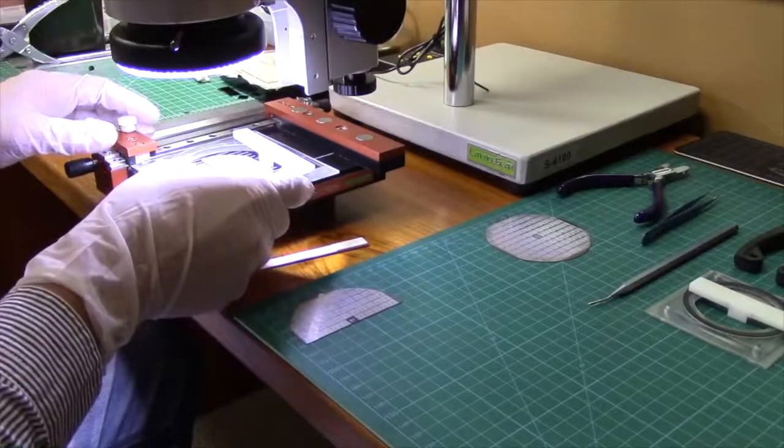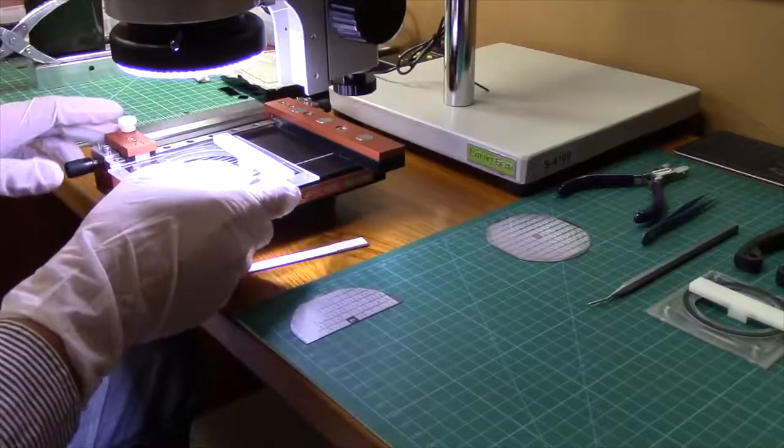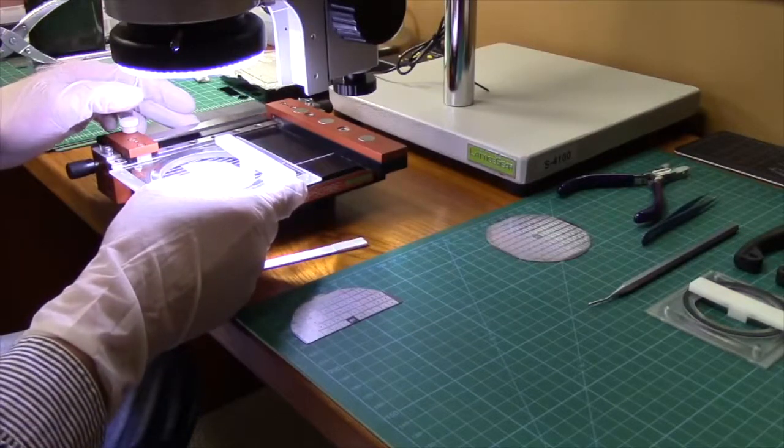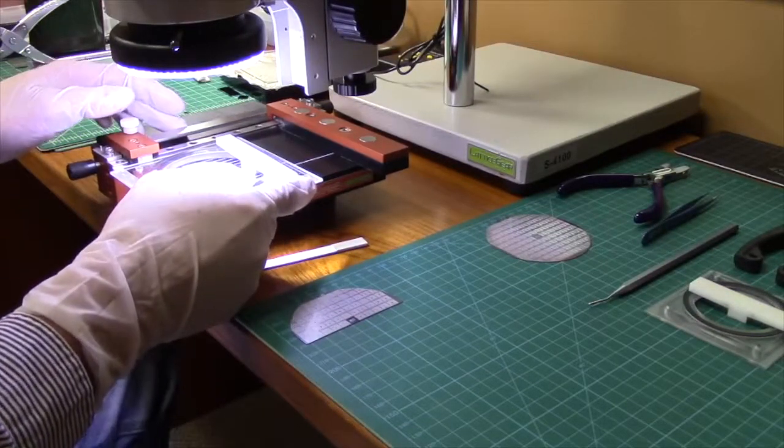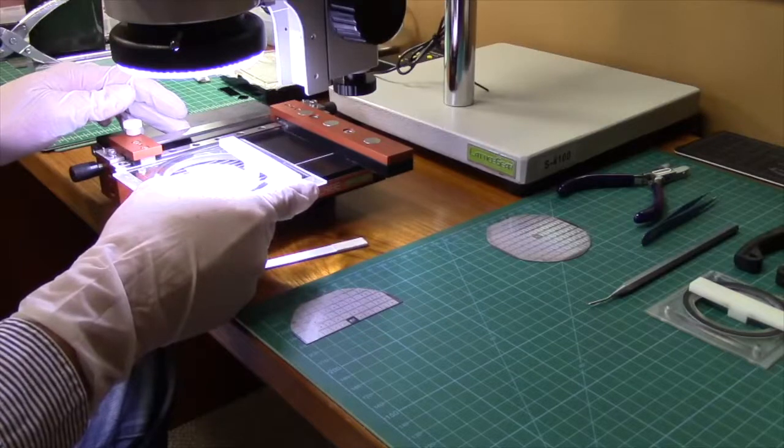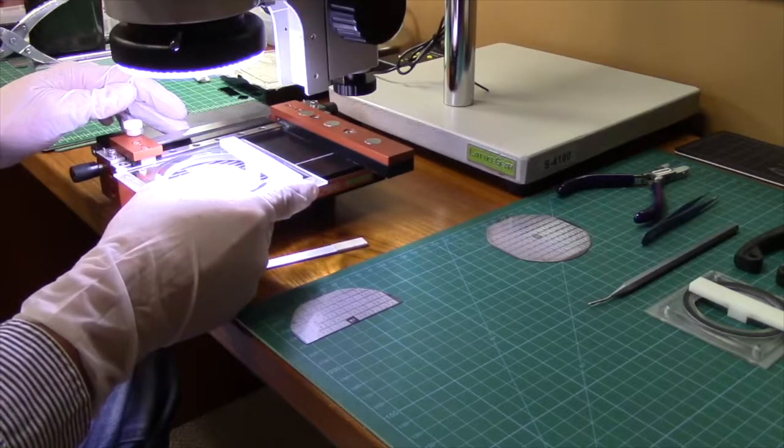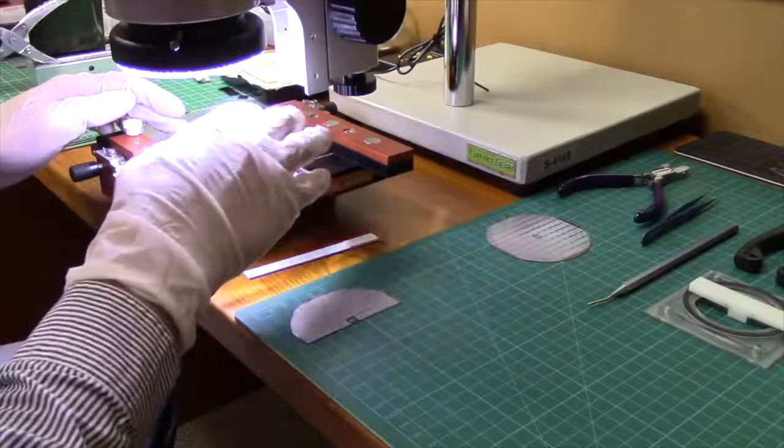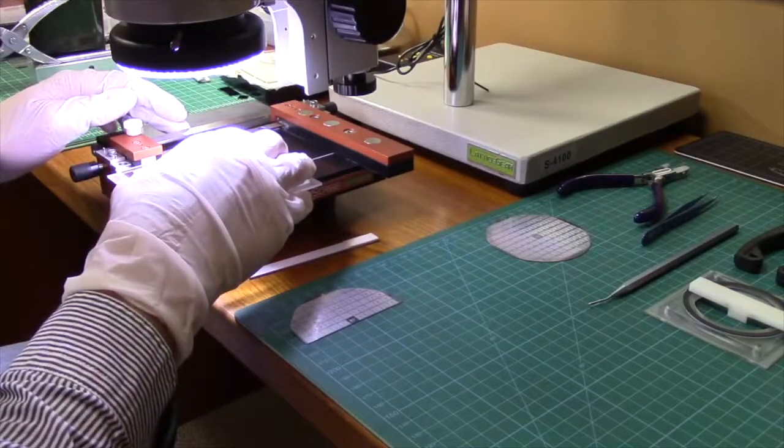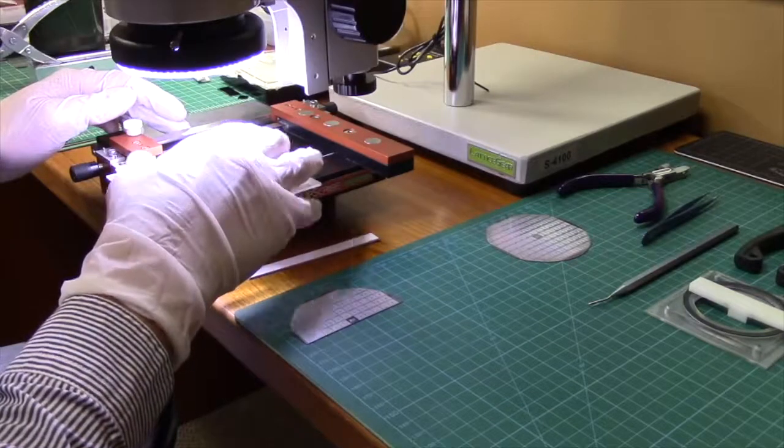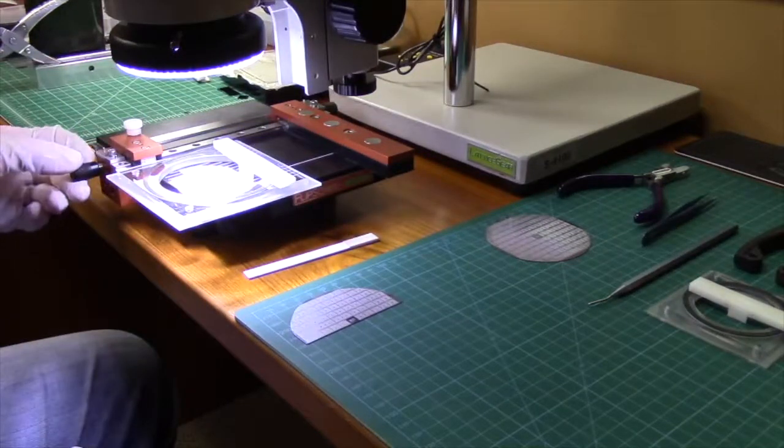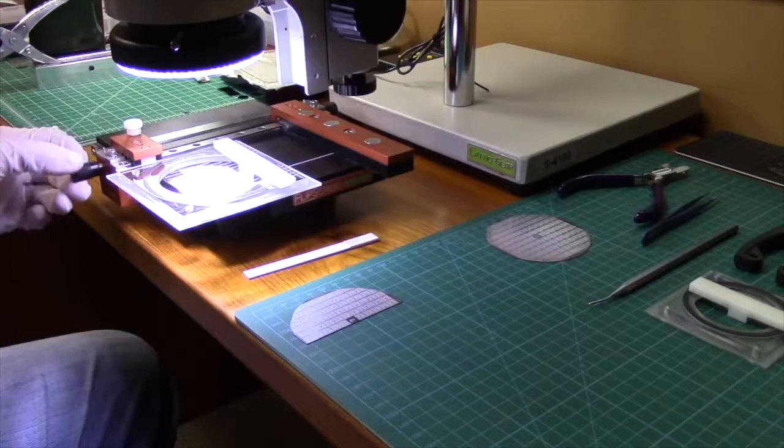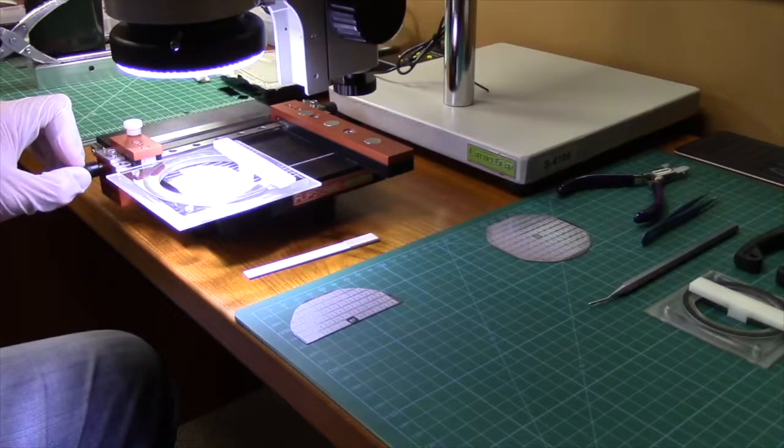With the scribe set, we will now align the guides to the location we wish to scribe. Using the stereoscope, locate the location you wish to place the scribe and align it to the scribe tip. For this example, we are using the lines between the dies patterned. Once aligned, lock the guide bar into place.